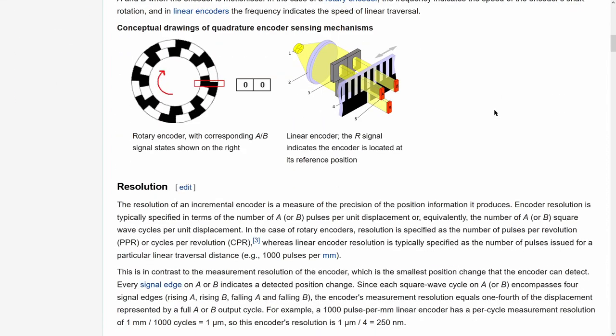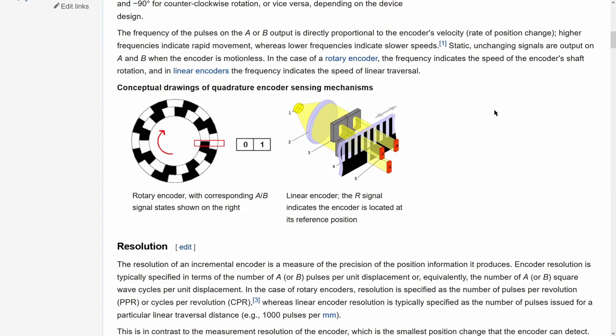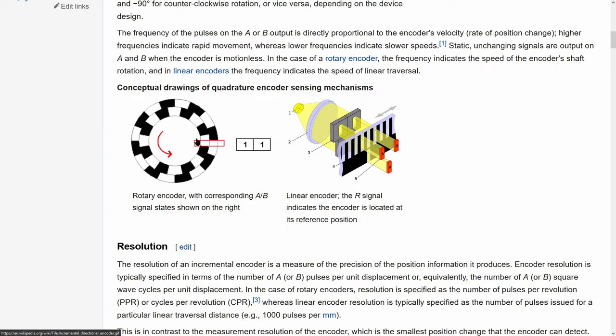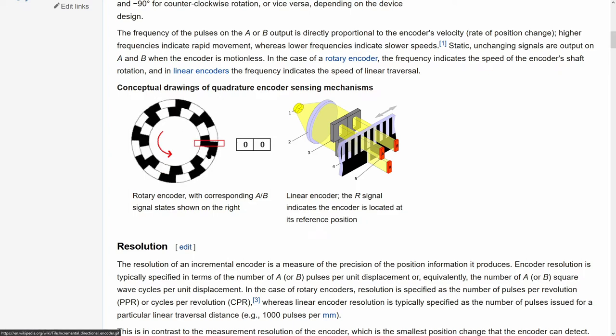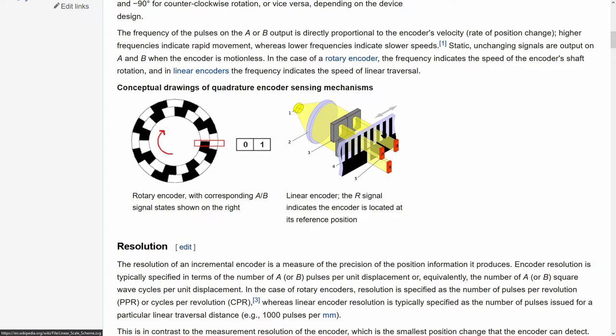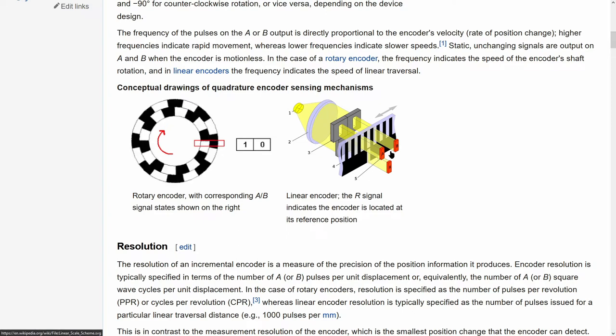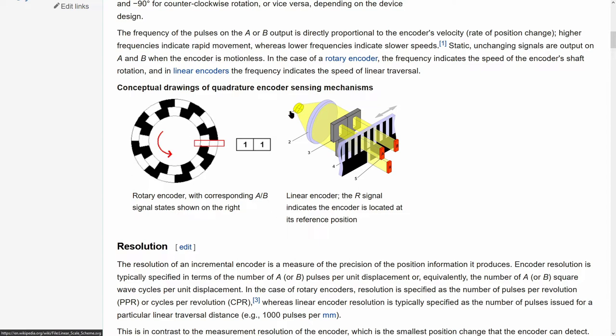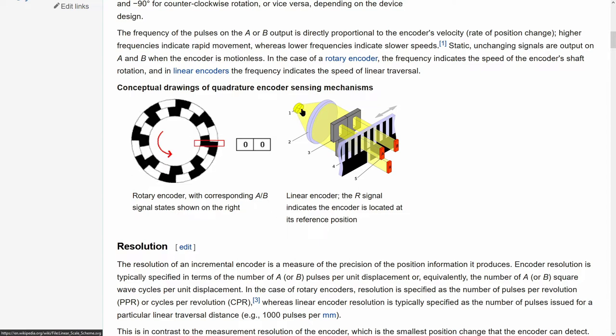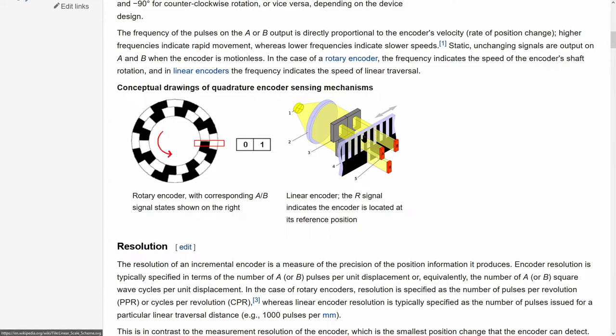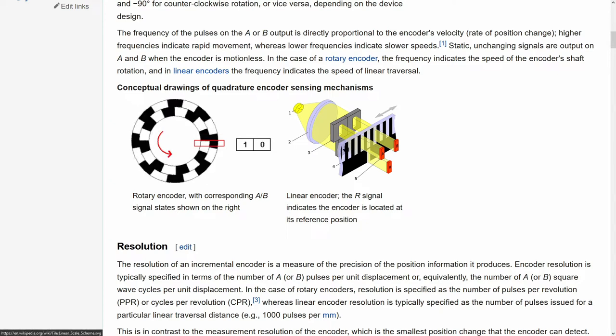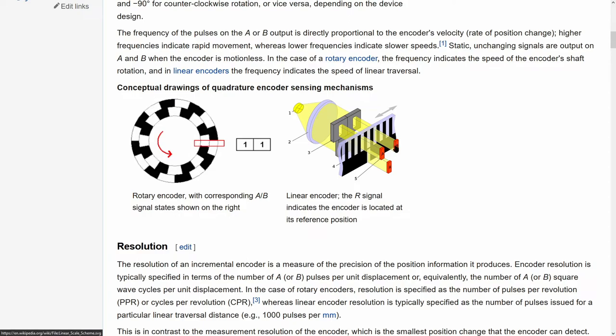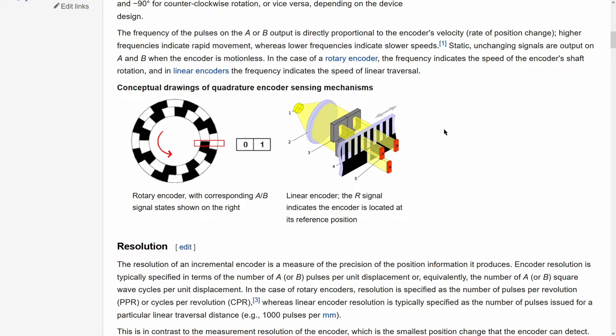The animation here is quite a good example. Obviously this is for a rotary encoder, however if you were to lay this horizontally along, it's the same pattern. This illustration here shows quite well the two channels that I was describing earlier. We have a light source which is the LED behind, it passes through a filter and then through the glass scale that I talked about with the patterns etched on, and then we have A and B which are the two detectors.